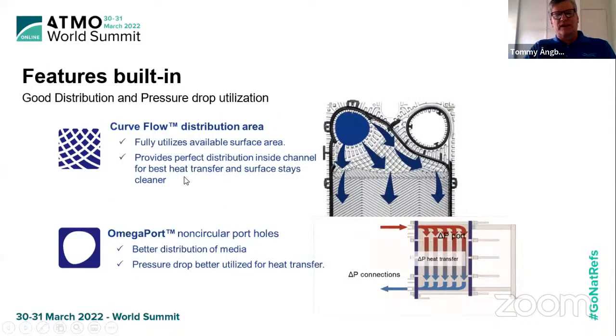How could we do it? It's not just saying you do a heat exchanger and you do it. You have to ensure a very good distribution over the plate width, to be sure that you have the superheating area, the condensing area, and the subcooling area in the heat exchanger. You also need a good distribution throughout the plate pack, and there we have constructed this omega port that allows good port pressure drop, allowing the flow to be spread all through the plate pack. And we have the curved flow distribution area, to be sure that we distribute the gas inside the heat exchanger. So this is built in for that type of condenser.